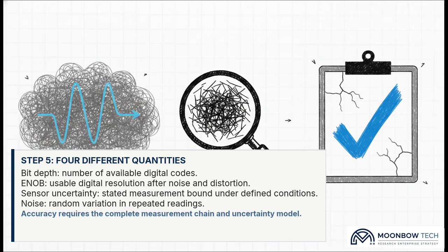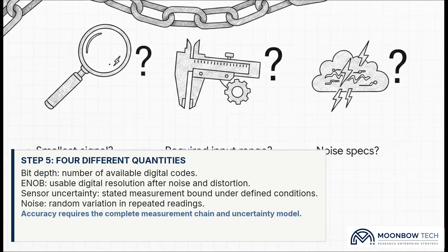If you confuse them, the practical consequences in a power quality lab are severe. With a weak chain, you might completely miss a real harmonic because it's swallowed by uncertainty. You might mistake random noise for a valid signal. Or worse, if you're operating near a strict laboratory acceptance threshold, these limitations can completely alter your apparent conclusion. To protect your data, you have to evaluate the entire chain holistically.